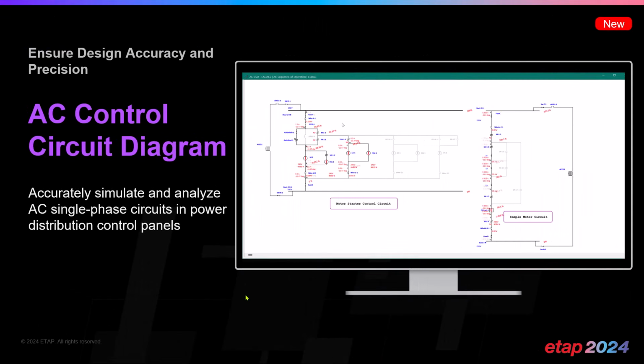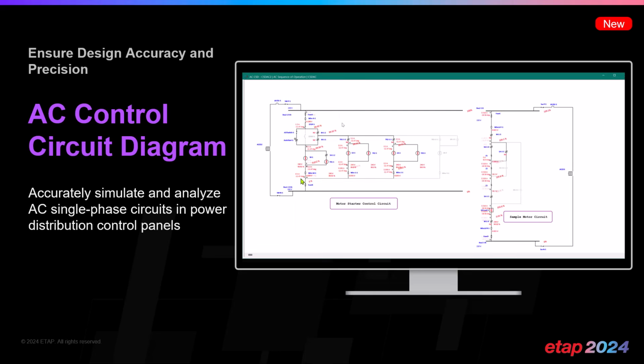We've also included AC control circuit diagram, and as you can see, when you use the AC control circuit diagram, it's computing the voltages as well as the sequences of the way a control circuit diagram operates, which includes, of course, the contacts, the solenoids, the Form C contacts, and because this is AC, we also include the power factor and the current angles associated with an AC control circuit. And this is connected to the ETAP single line diagram.